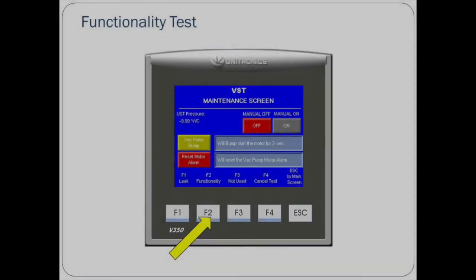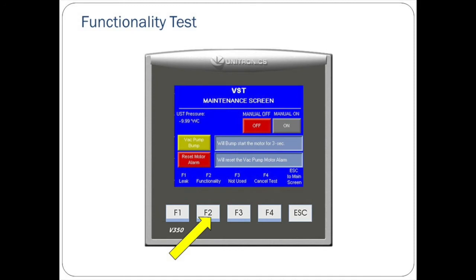Functionality test. The functionality test is the most comprehensive test that exists for the Green Machine. In passing this test, the Green Machine will demonstrate that everything internally is functioning correctly. Before beginning the functionality test, be sure that all lockable ball valves between the Green Machine and the vent risers have been closed, all caps from the 3 T-fittings have been removed, and that the three-way ball valve below the pressure sensor is turned to the off position.